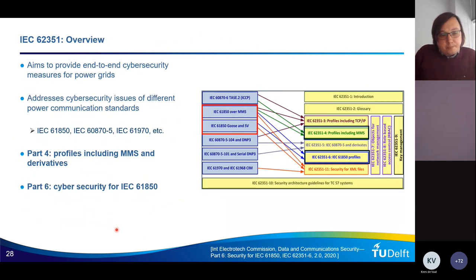Now, let's also look, in the 4 minutes that are left from our webinar, at what the mitigation techniques would be. So we observed the impact. Well, we already have a communication standard called IEC 62351. And this aims to provide end-to-end cybersecurity measures for power grids. This standard addresses cybersecurity issues for different power system communication standards, including IEC 61850.